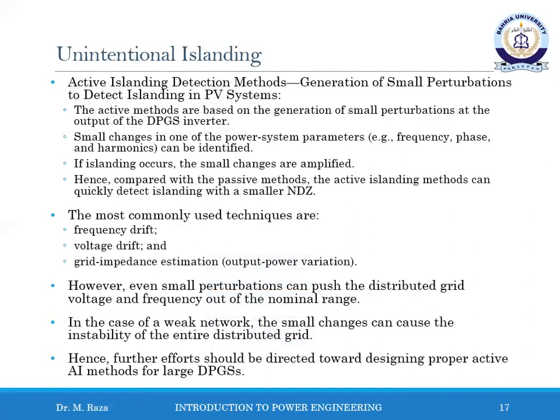Active islanding detection methods are based on the generation of small perturbations at the output of distributed power generation system inverters. Small changes in one of the power system parameters, such as frequency, phase, and harmonics, can be identified. If islanding occurs, these small changes are amplified. Hence, compared with the passive method, the active islanding method can quickly detect islanding with a smaller NDZ area. The most commonly used techniques are frequency drift, voltage drift, and grid impedance estimation.